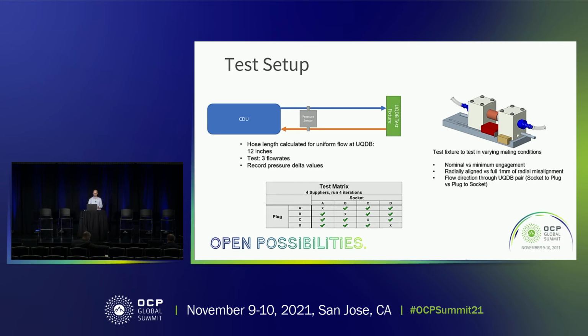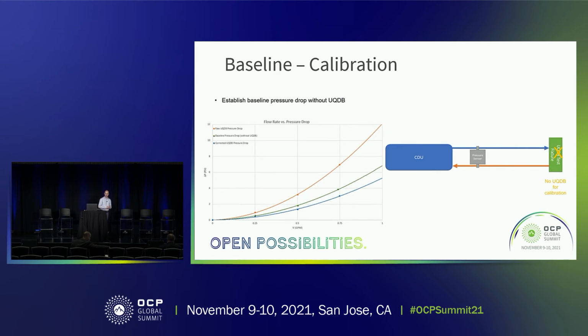So now to get into more the procedure of the testing. As you can imagine, if you're pushing fluid through that fixture I showed you that changes alignment, as well as this length of hose, there's going to be some inherent pressure drop within your system. And if you don't account for that, then you're not really understanding what the pressure drop through the quick disconnects truly is. So you can see here the green line on the graph represents what we call our calibration run or your tare run. Really, it's just the pressure drop through your system. You run the same test recipe, essentially just without any quick disconnects, using a straight flow adapter, and that'll give you the pressure drop of that system.